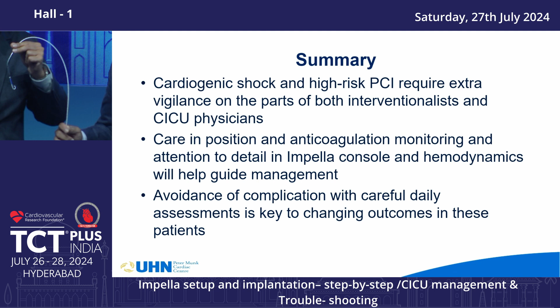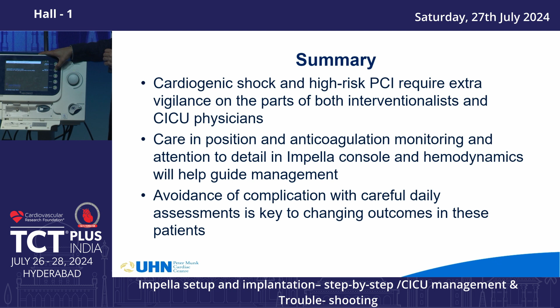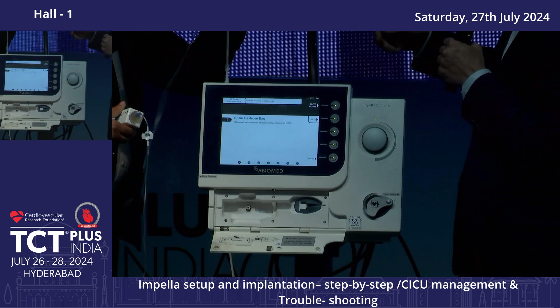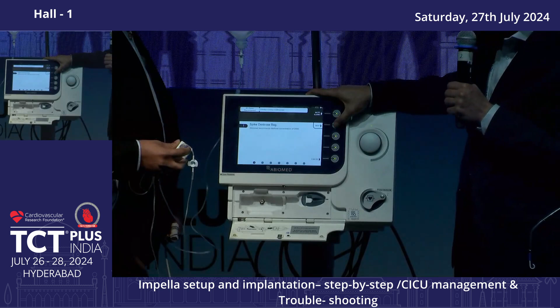Well, here's how. First, you press this little button on the side and you release the door that covers the cartridge, which is going to be your purge, okay? You click on Start New Case. And so the first thing you do is spike the dextrose bag. That's going to be part of your purge solution. It creates the hydraulic barrier within the device to ensure there's no blood that gets in the motor. Once you've spiked the dextrose bag, you press Next, which makes life pretty easy.